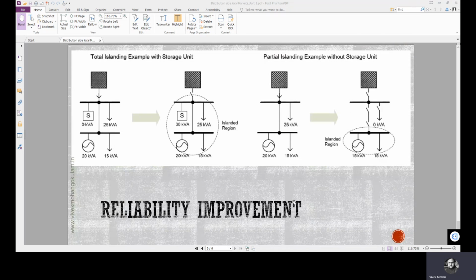Now in the last case, reliability improvement. How to improve reliability with the help of local generation or local load, or in general broadly with the help of a microgrid. So in the first case we have a storage device, but initially there is no output from the storage device, but we have two local loads, 25 kVA load and 15 kVA load. 20 kVA is the local generation. But total load is 40 kVA. So the remaining is taken from the upstream grid.